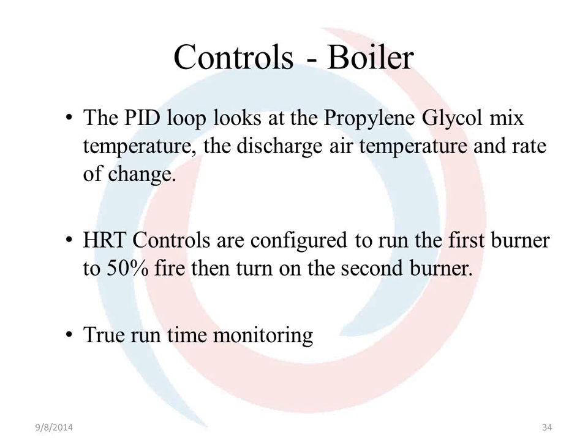By limiting the maximum fire of each of the burners to 50% until all the burners are on, it also helps to maximize efficiency and ensure all boilers are condensing. At part load, the boiler efficiency improves due to the larger surface area compared to the BTU input, allowing for more heat transfer. In order to ensure the maximum life expectancy, the runtime of each burner is monitored and the primary burner is rotated so that the burner number 1 is always the one with the least amount of runtime.